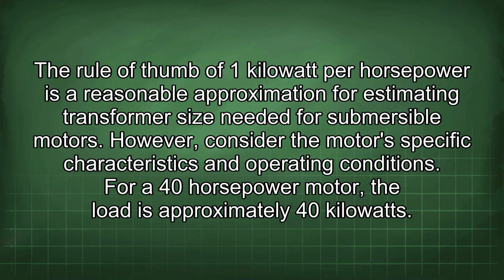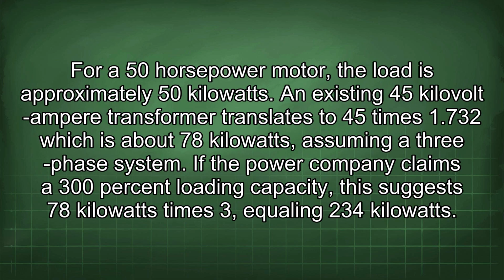The rule of thumb of 1 kilowatt per horsepower is a reasonable approximation for estimating transformer size needed for submersible motors. However, consider the motor's specific characteristics and operating conditions. For a 40 horsepower motor, the load is approximately 40 kilowatts. For a 50 horsepower motor, the load is approximately 50 kilowatts.